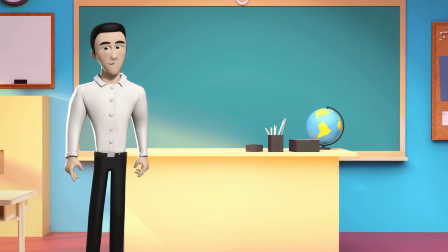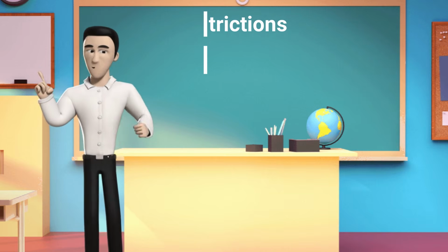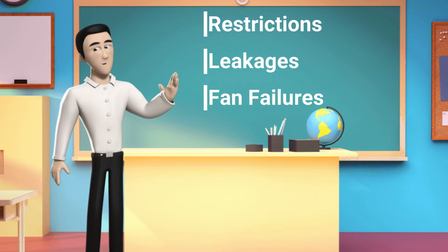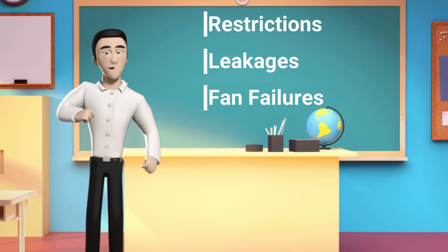So to recap, check and clean out any airflow restrictions. Check for loose or leaky gaskets. And make sure the combustion fan is working as intended.